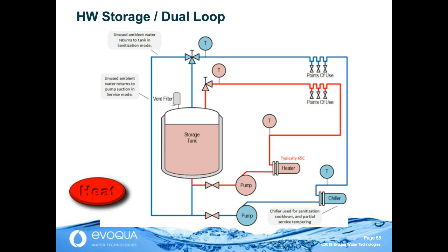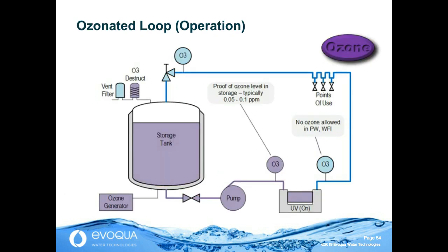If we look at an alternative, and this is very practical with membrane-based systems, although the product water could be heated, one of the case studies I showed you, the product water was heated and stored at 80 degrees C. But in most cases, the water is going to be stored at ambient, and ozone is highly recommended in that EMA guideline for non-distillation-based systems.